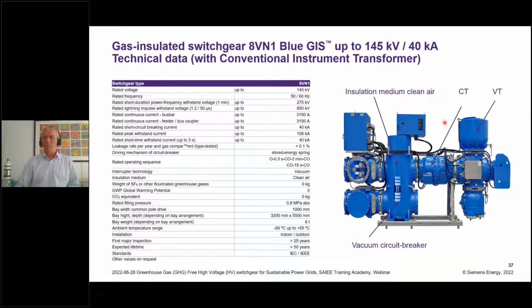This is the big brother, the 145 kV GIS, and here the aluminum compartment is just shown, that was taken out to show that there are 3 vacuum interrupters standing in here. On top is the proven spring type drive, which drives that. And here you see the different compartments which are well known from the normal SF6 technology. So the overall view looks identical to today's SF6 technology.